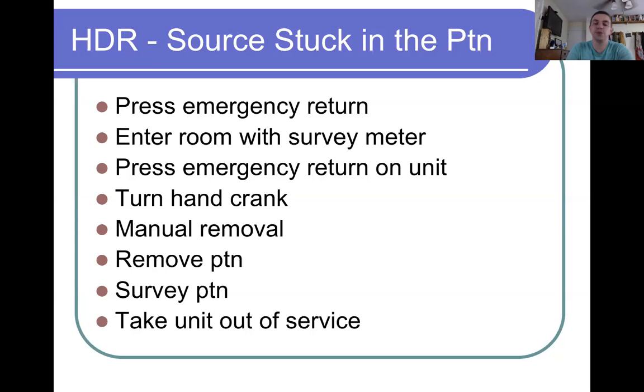And unfortunately, we have had situations like that in our hospital where the source is not where it is expected to be, whether it is a fault of the machine or a faulty catheter length. But there's also the situation where the source, after the treatment time, whether it's a couple of seconds or a minute, fails to return to the shielded afterloader. That's a big problem because the 10 curie source is putting out a lot of radiation very quickly. So if you are the physicist or the physician administering an HDR treatment, you have to be prepared to, if the source does not retract, quickly enter the room and manually pull the source out of the patient. There's an actual manual crank that will pull the source back into the afterloader.